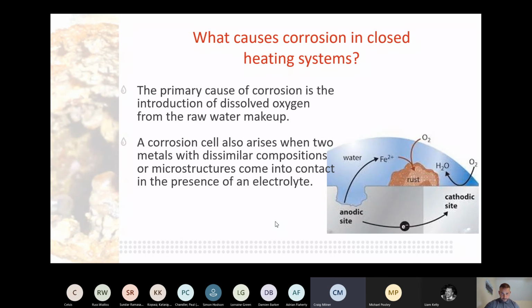This one, basically what you've got is a cell that forms like a battery. So you've got an anodic site and a cathodic site. The anodic site, if you see a pipe with holes in the pipework, that's where the anodic metal is being given off. And then when you get the lumps and bumps forming on the pipework, that's on the cathodic site. But all that debris that's forming up has been released, and it's come away from the pipework or valves or other associated equipment within. So you can tell quite quickly if you're pitting or where your anodic areas are and where your cathodic areas are. It's a really simple way of looking at it, but you get lots of buildup of debris, and that's all debris that's been released from other parts of the metal in the system.